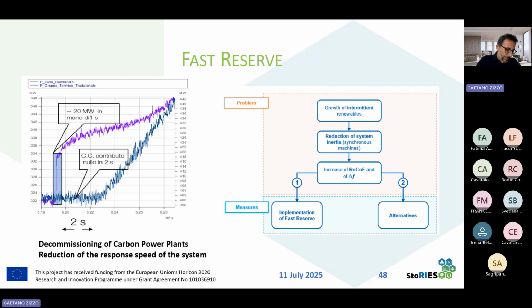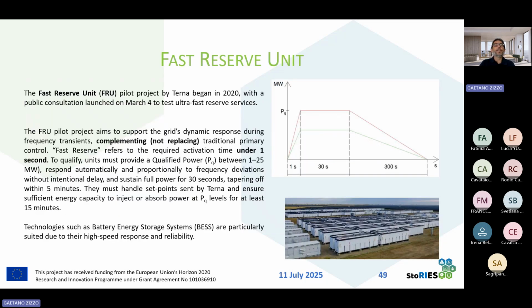Another application that I show you is the fast reserve. We already talked about fast frequency regulation provided by batteries. This is a real project implemented in Italy. Since in the next years we will dismiss a lot of old power plants, we will lose the regulation response and the inertial response of these plants. So we must replace the inertia of these plants and the fast response in the primary frequency regulation, and we will do it using storage systems that will be installed in various parts of the country. There is a plan to install them in Sicily, in Sardinia, and in southern Italy and northern Italy.